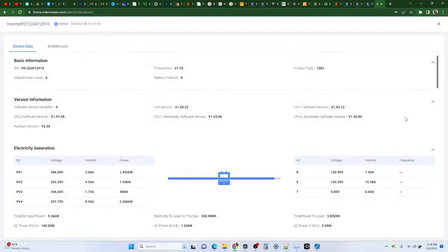Ray says DIY batteries or off the shelf. Man, I can't say one's better than the other. DIY is less expensive, but even me, I'm kind of trying to get away from the wood-case-strapped-together DIY battery. I've sourced these rack mount cases that I can put batteries in. It's going to be more expensive than doing something with wood or something on a shelf, but it's so much more modular. If I was doing a large, like 100 kilowatt hour battery, I would probably invest in shelving or cabinets that I can just mount the batteries directly into. But if it's something mobile, or something I need to be able to move, rack mount's good. I like rack mount.